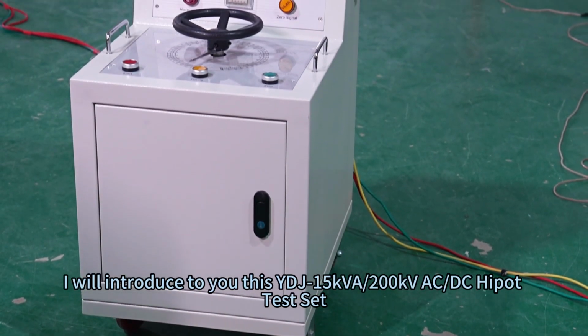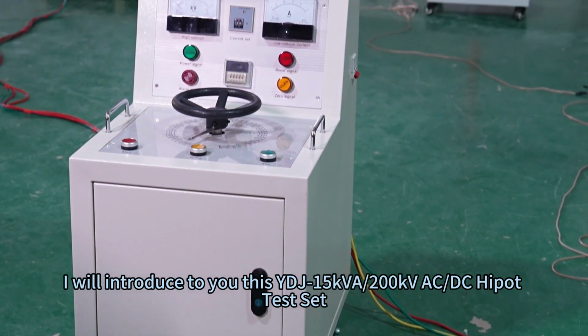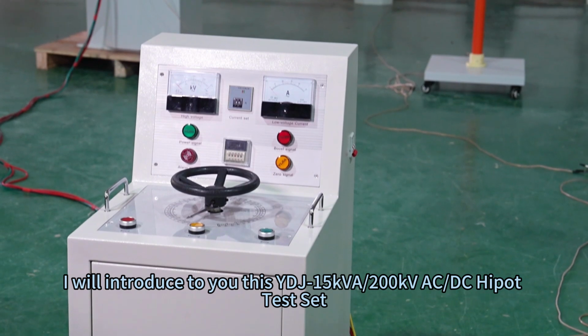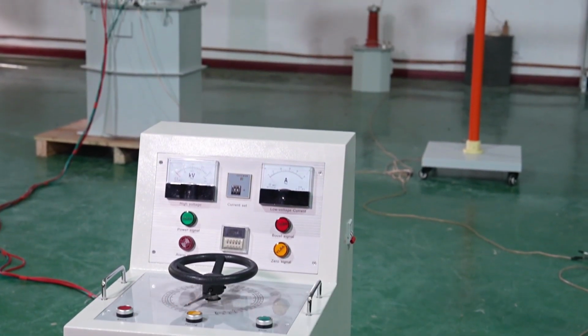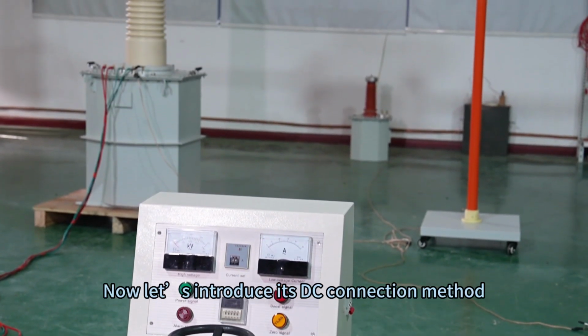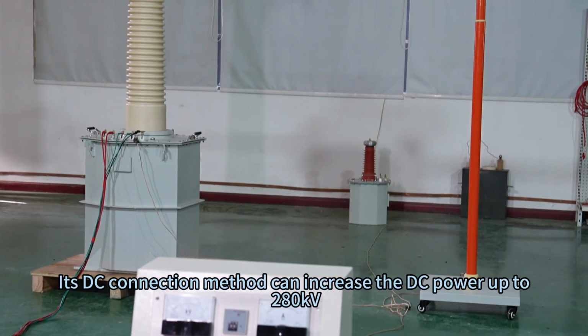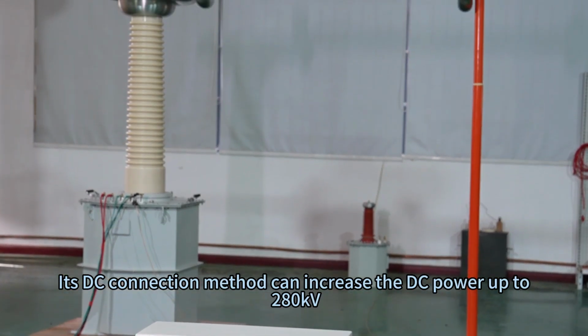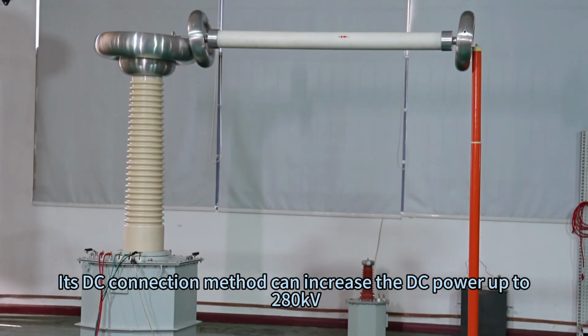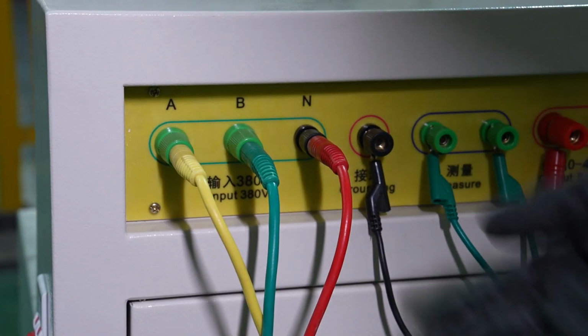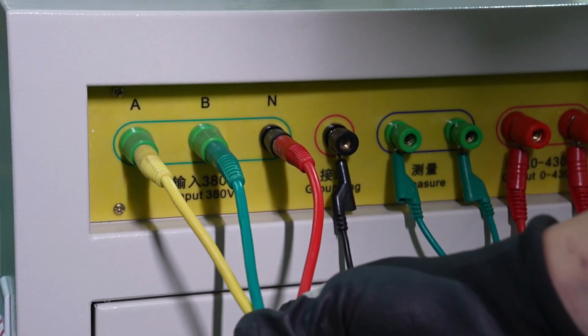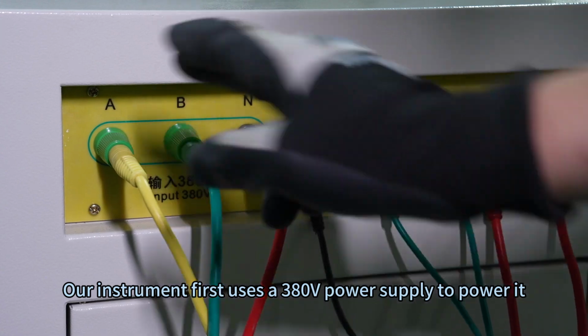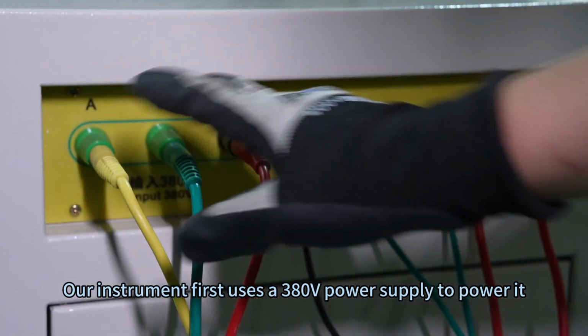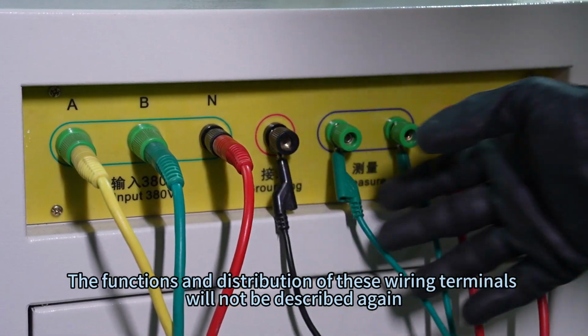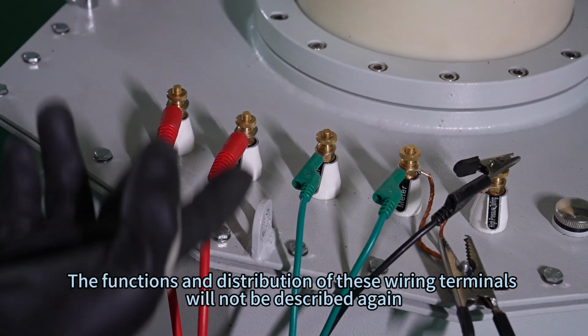Next, I will introduce to you this YDJ-15kVA/200kV AC/DC Hipot test set. Now let's introduce its DC connection method. Its DC connection method can increase the DC power up to 280 kV. Our instrument first uses a 380 V power supply to power it. The functions and distribution of these wiring terminals will not be described again.